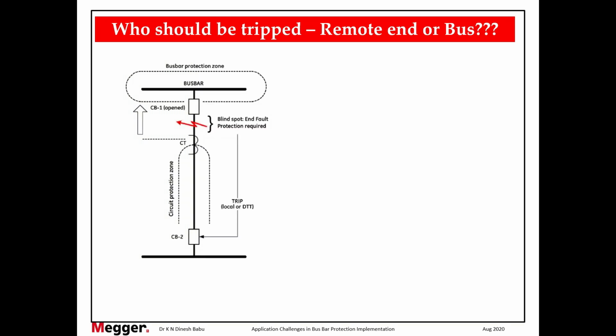The next one: who should be tripped, remote end or bus bar? Let's analyze this very interesting concept. Bus bar, followed by breaker, after that your CT. Now there is a common question which comes to everyone's mind: if the fault occurs between CT and the breaker, what should I do? So this is an example. Fault occurred between CT and breaker. Now what happens? According to the breaker, this fault is an external fault, not a bus fault. But according to the CT, this fault is a bus fault. That is the first point. Second, this fault is at the backside of the CT. So the distance protection which is connected to this CT will not sense this fault in the forward zone. It will be a reverse zone fault.